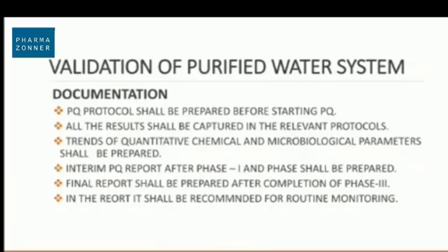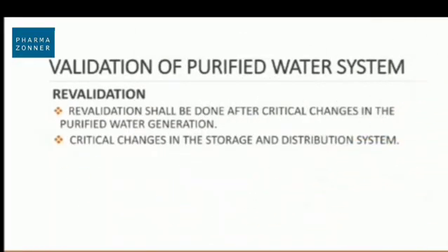The final report shall include recommendations for routine monitoring — including sanitization frequency, critical parameters to be recorded, and alert and action limits if not previously defined. All these recommendations should be mentioned in the recommendation section of the purified water system report. Revalidation of the purified water system depends on changes made to the system. If any critical changes occur in storage and distribution, revalidation of the system is required.